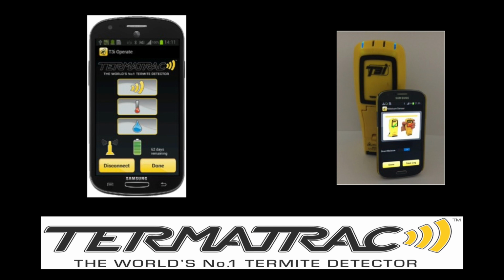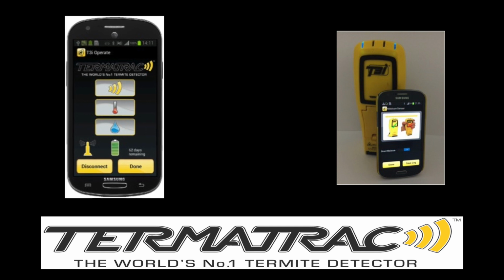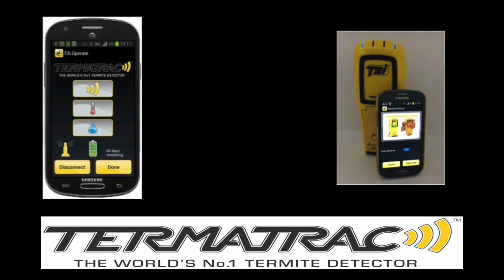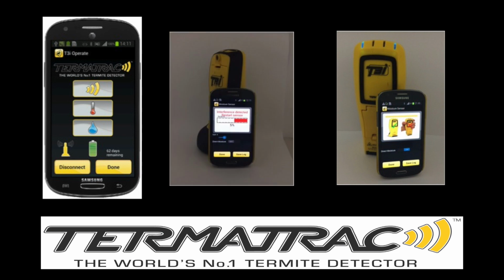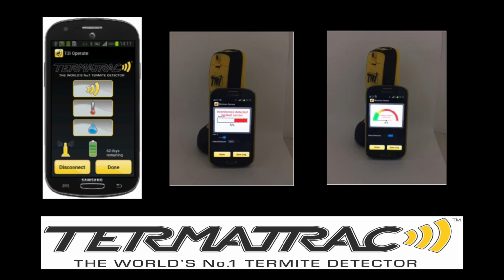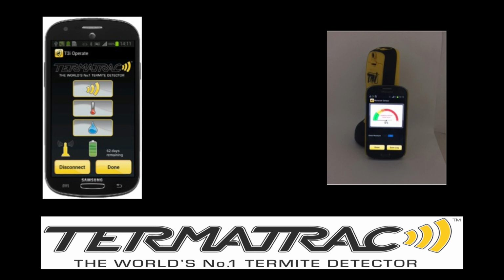When connected, the T3i moisture sensor does a self-calibration. This calibration will take into account the specific ambient humidity of the day. At this point, the moisture sensor needs to be open to the air. Should any interference be detected, an alarm will sound and you will also have a message on the screen indicating this. You will need to exit the moisture mode and restart it, allowing it to go through the calibration process in the upright position.